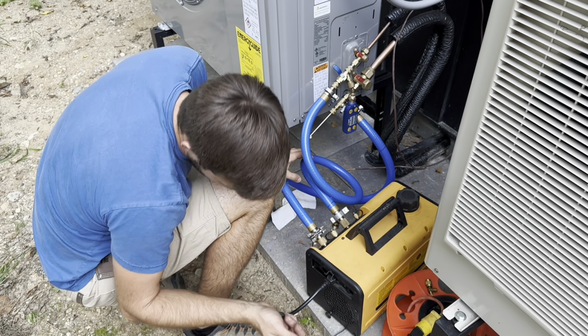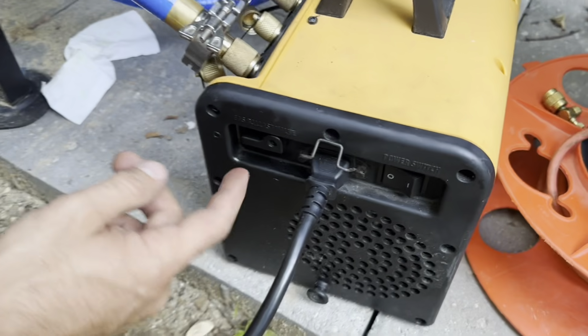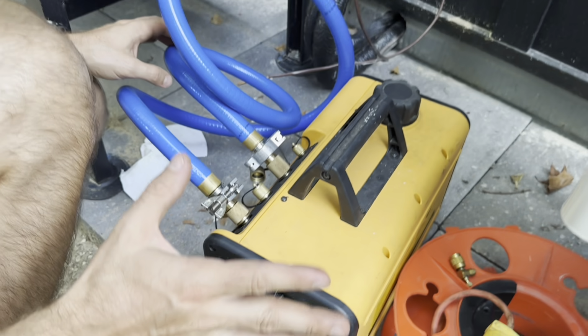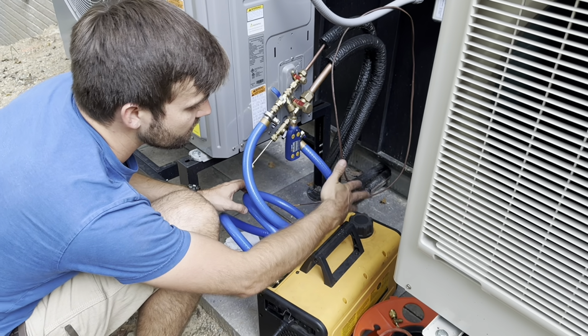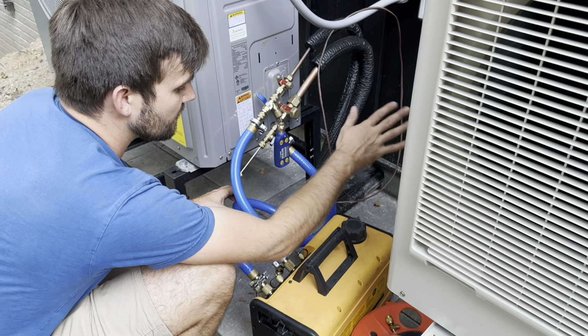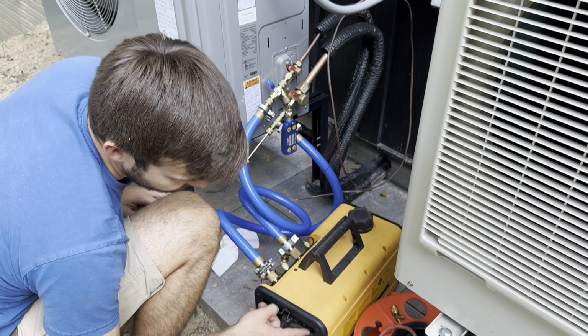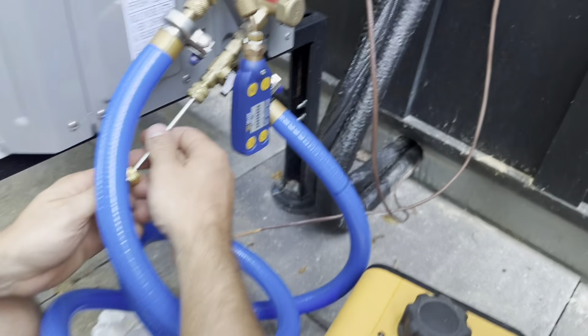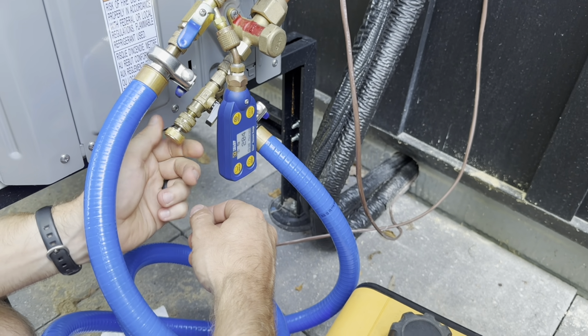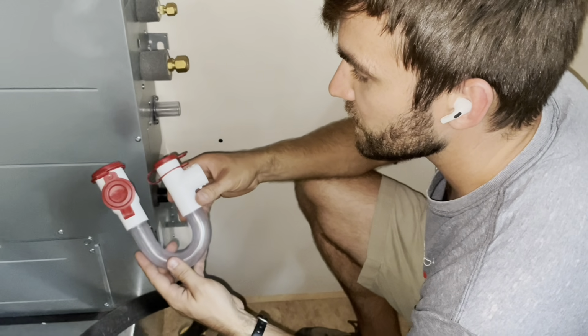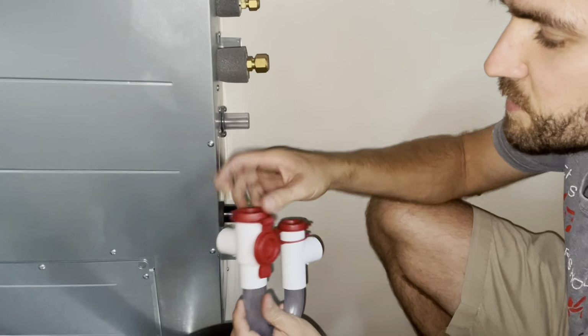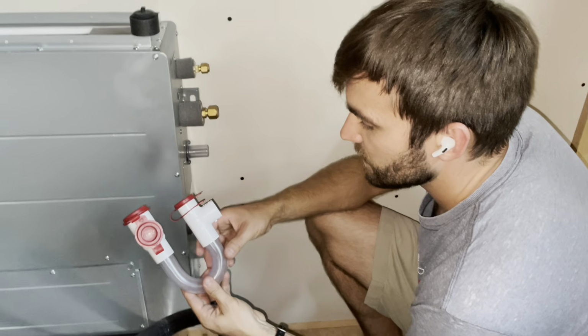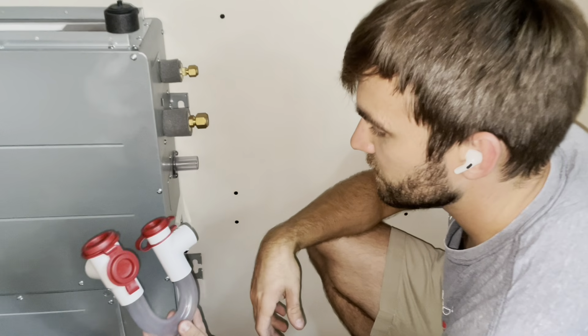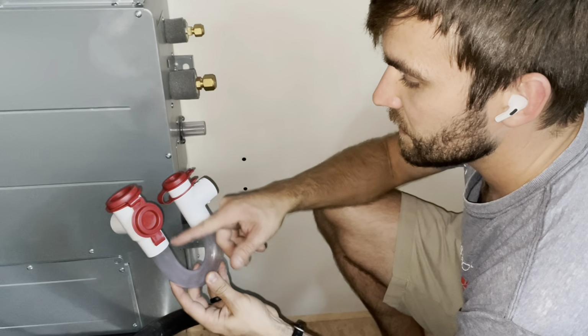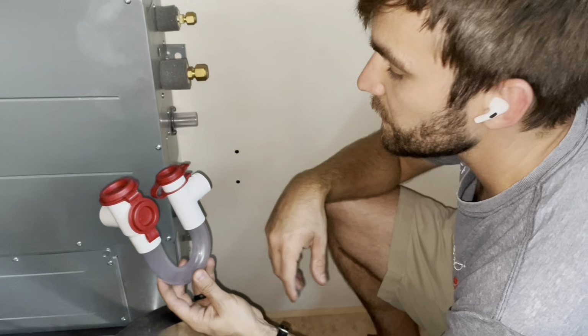Hooked up, got the ballast valve open, so when you're pulling a vacuum and you're above 1500 microns, you keep the ballast valve open and it pulls the vacuum faster and keeps impurities from getting in your vacuum oil. Not all pumps have that. I really like to use these easy traps from Rector Seal because they have all these caps so you can just pop open to clean them, and they come with a brush, and you can tell if they're getting dirty because they're clear. Real nice. And they're a very deep trap, so there's no chance that the unit will suck the water out of it.